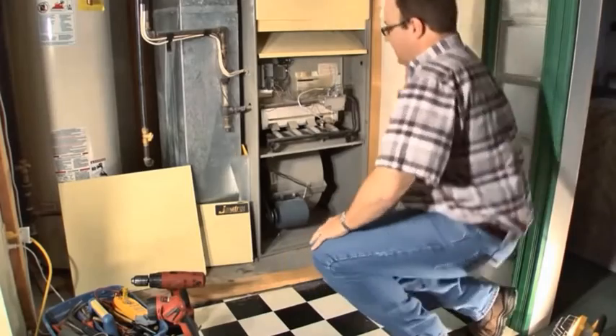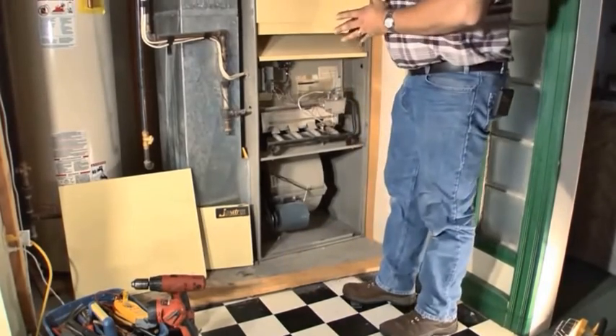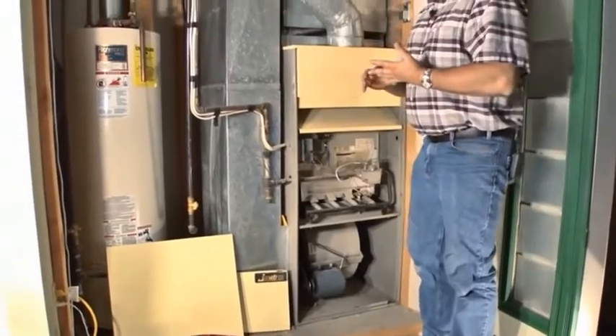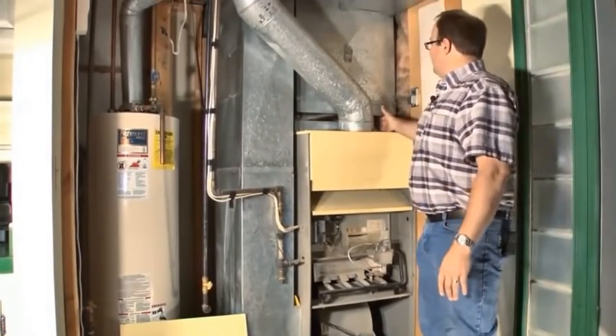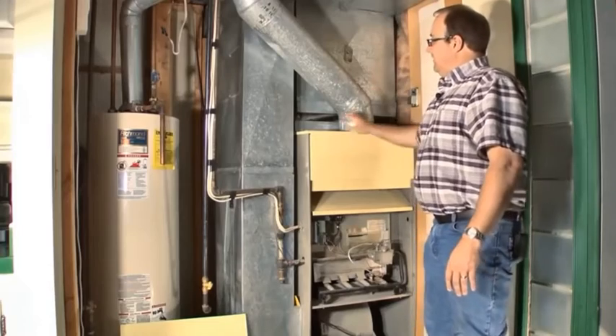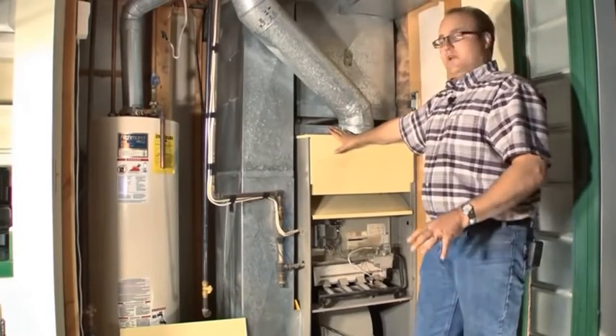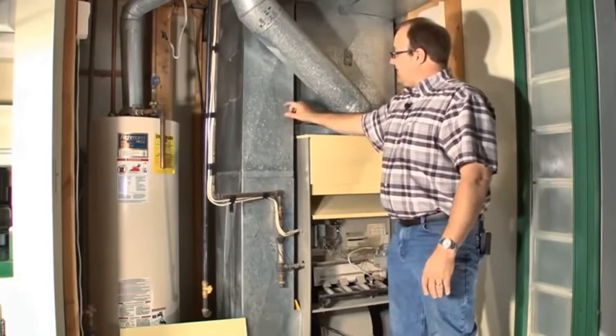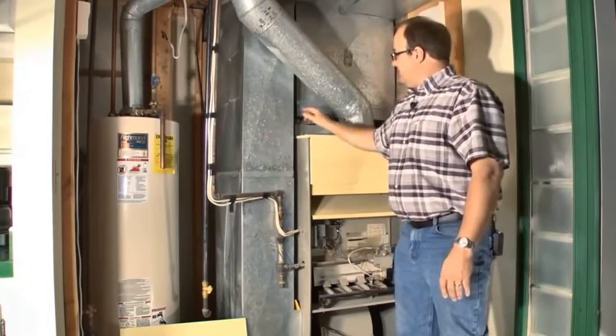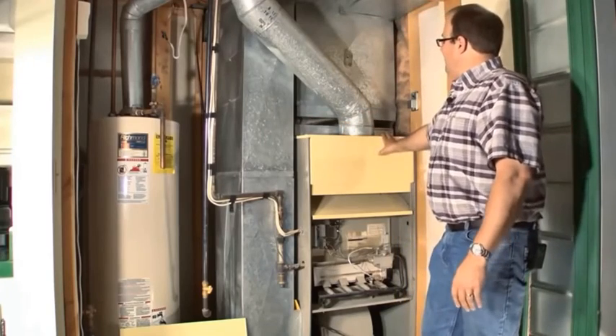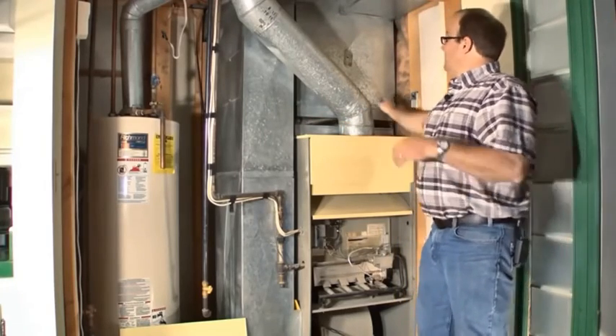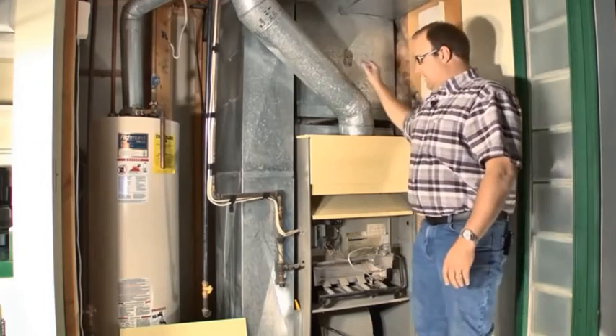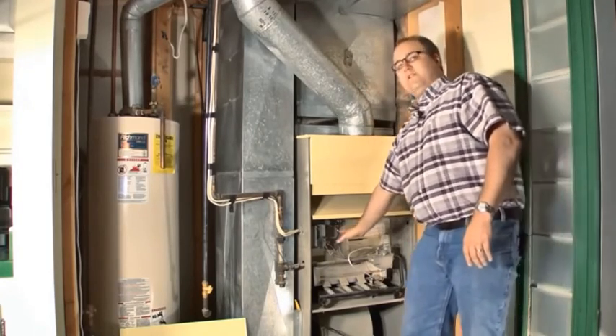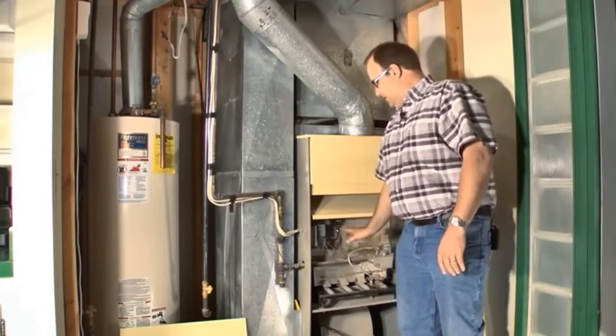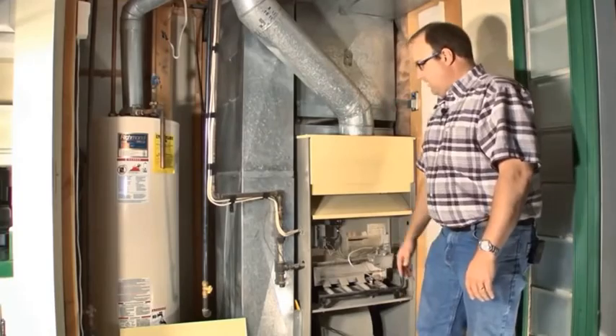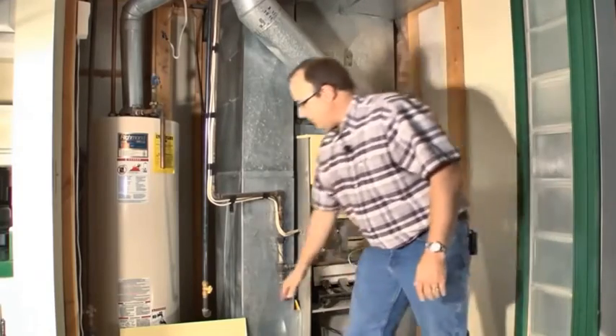So anyhow, we'll go ahead and put the covers on. We're going to measure a few temperatures here. One is the temperature of the air when the fan comes on. After about 5 minutes of runtime, we want to get the temperature of the heat rise. That's the difference between the return air and the supply air. And then after we turn the furnace off, we're going to get the fan off temperature, which should be about 95 degrees because we adjust that from this control here. I'm going to put the covers back on and then we'll do that.